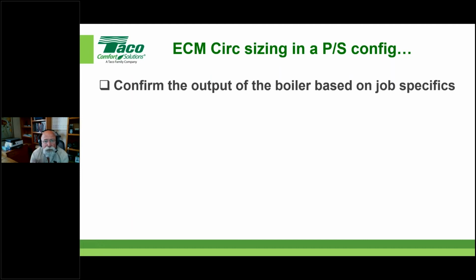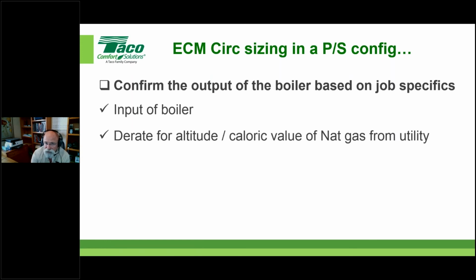Okay. Confirm what the output of the boiler is based on the job specifics. We need to know what the input is. We need to know, is there any derate for altitude, caloric value, or anything like that? A lot of times the natural gas utility will tell you what their caloric value is. For those who don't understand, that is how many BTUs a cubic foot of this gas can produce at that given altitude. That's more accurate typically, because then you have something from the people who are selling you the gas and are putting the recipe together, so to speak.